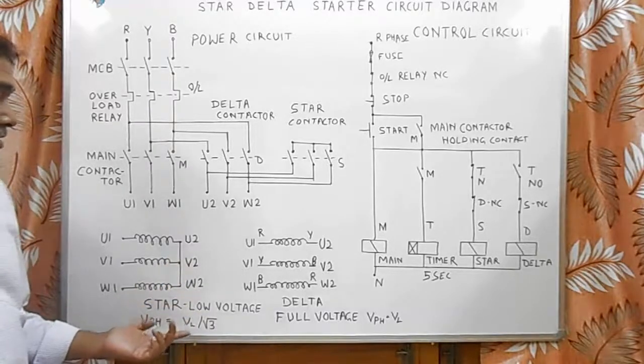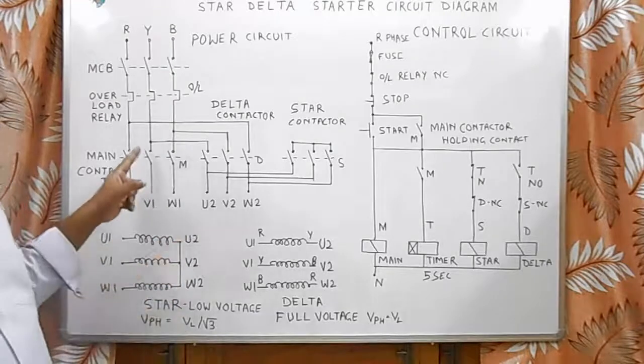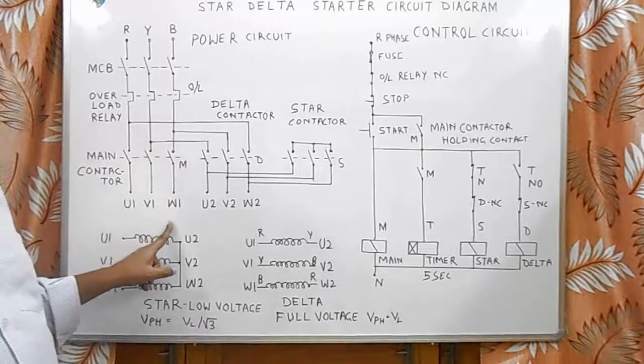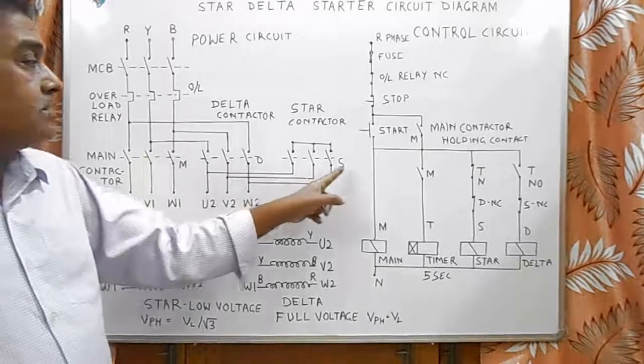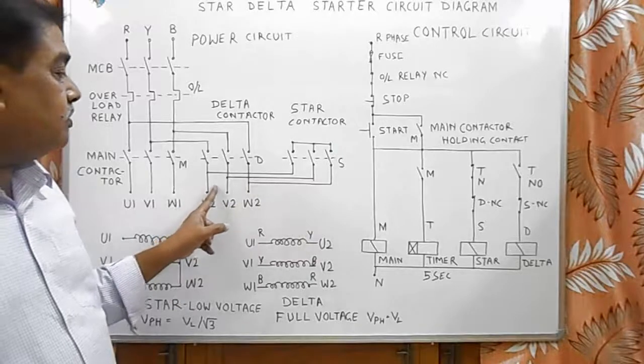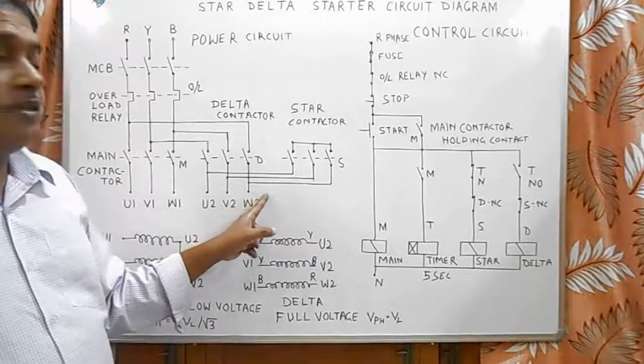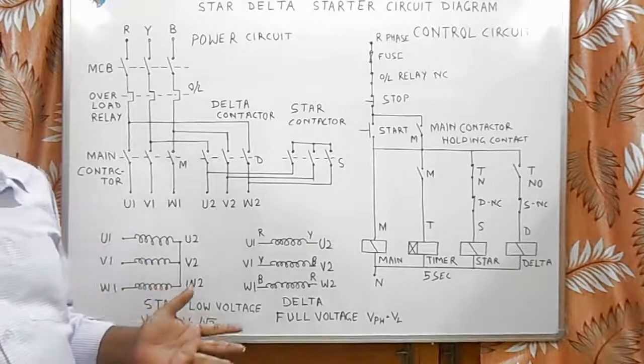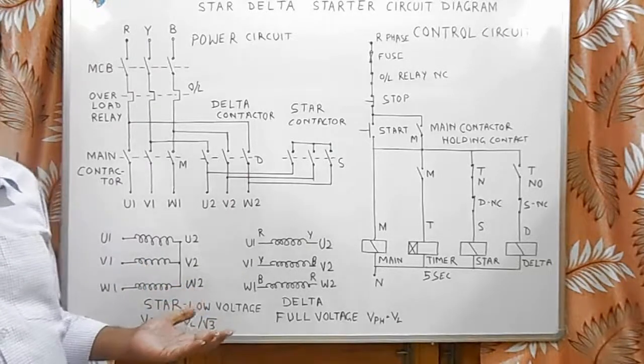For obtaining this star connection, we use main contactor to give supply to U1, V1, and W1, and use star contactor to short-circuit U2, V2, and W2. With this scheme, we achieve star connection and start the motor at low voltage.